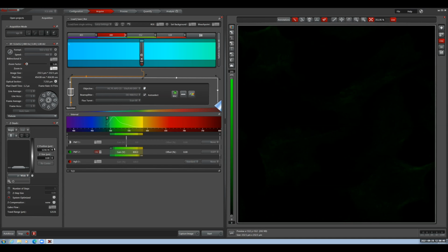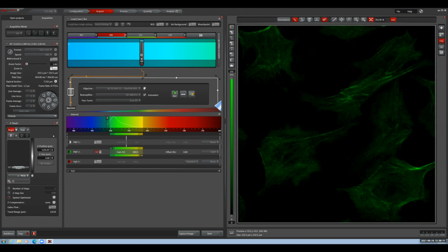We're going to do a Z stack, which means we go through the whole cell with a series of optical sectioning, but we need the bottom one. So now I say begin here. I hit this begin button. Okay, everything's still going live. I'm going to now scroll up. I'm using my Z position on my bar. You could also use the white little joystick. And now I just go through the sample sort of quickly. It's just live. I'm not gathering, I'm not saving information.